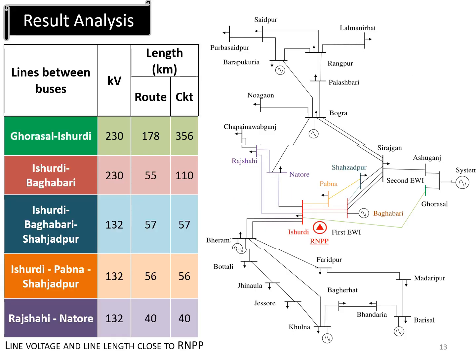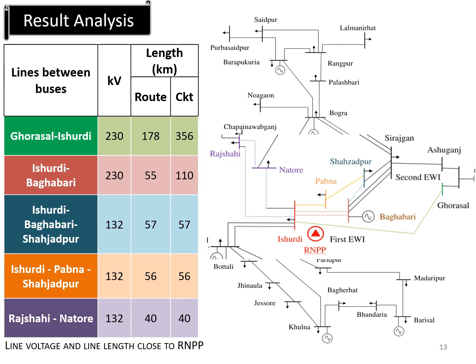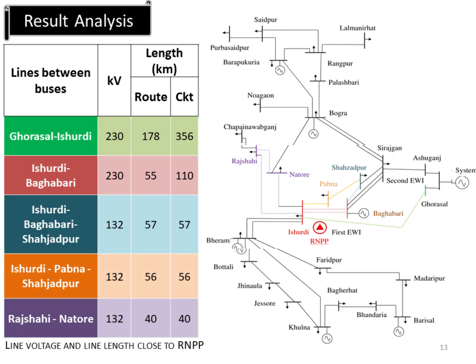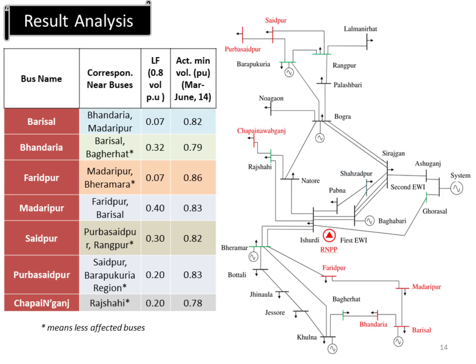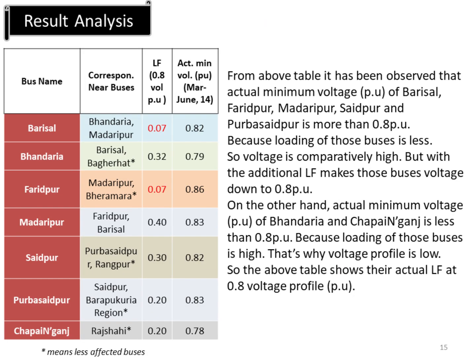This table lists key transmission lines near Rooppur, including voltages, lengths, and route circuits. Long lines like Ghorasal-Ishurdi, which length is approximately 178 km, are especially vulnerable to voltage drops, impacting nearby buses. The table shows loading factors and actual minimum voltages for selected buses. Buses with low loading, like Barisal and Faridpur, maintain voltages above 0.8 per unit. However, buses with high loading, such as Bhandaria and Chapainawabganj, already operate below 0.8 per unit. This indicates that even small load increases could push these buses into critical undervoltage conditions.